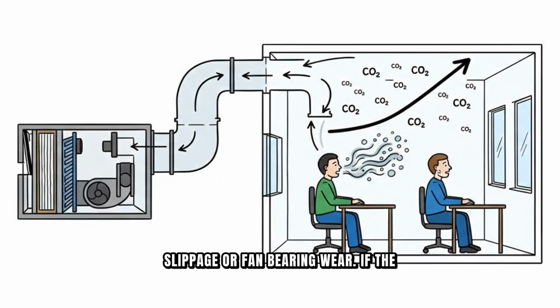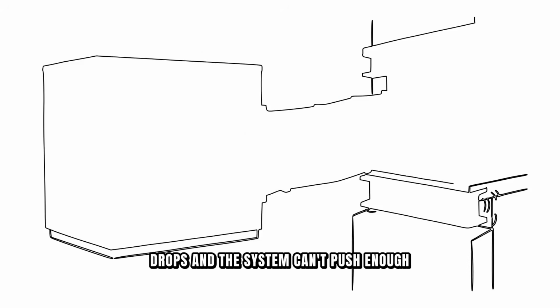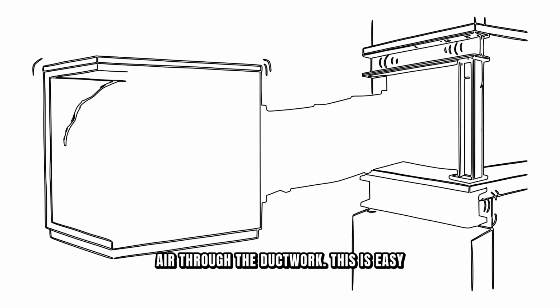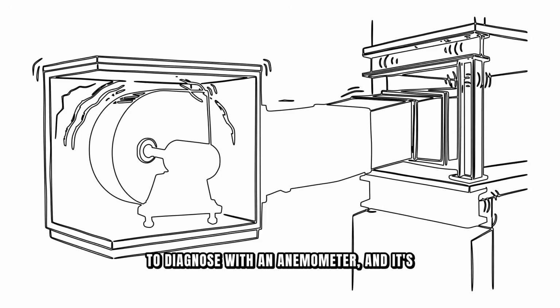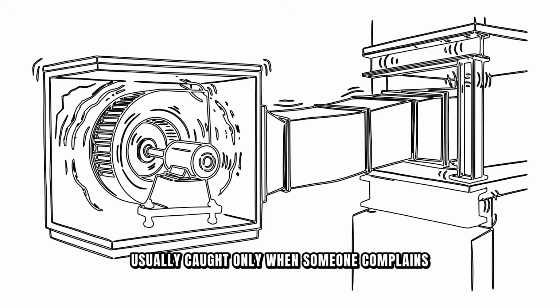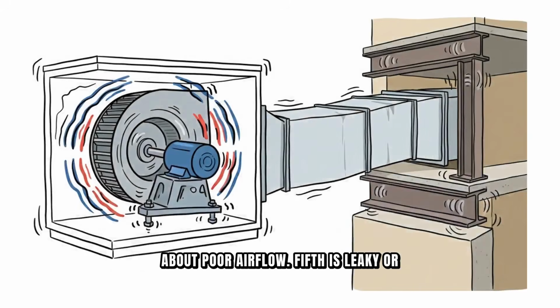Fourth is belt slippage or fan bearing wear. If the fan motor isn't turning at the speed it should, discharge static pressure drops, and the system can't push enough air through the ductwork. This is easy to diagnose with an anemometer, and it's usually caught only when someone complains about poor airflow.